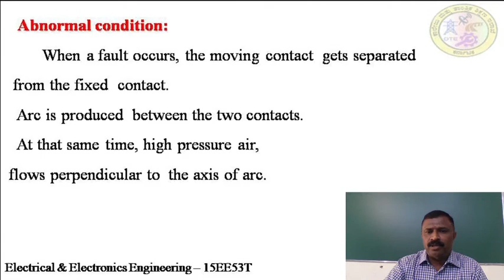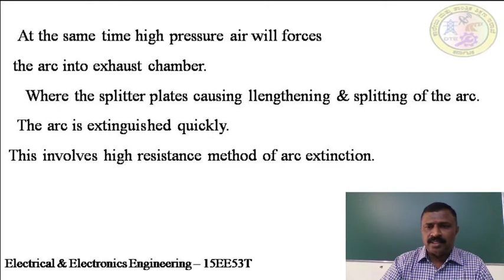At the same time, high pressured air flows perpendicular to the axis of the arc. This high pressured air forces the arc into the exhaust chamber, where it is provided with arc splitters and runners. The arc splitters and arc runners lengthen and split the arc. Lengthening increases the resistance of the arc. Splitting reduces the cross-sectional area of the arc. So when you go for lengthening and reduction of cross-sectional area, the arc gets extinguished quickly. This involves the high resistance method of arc extinction.